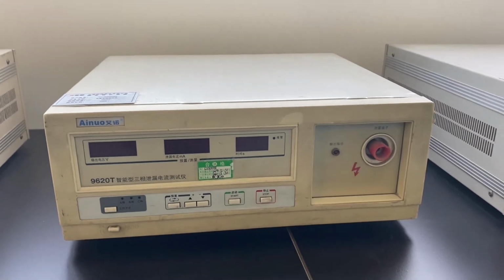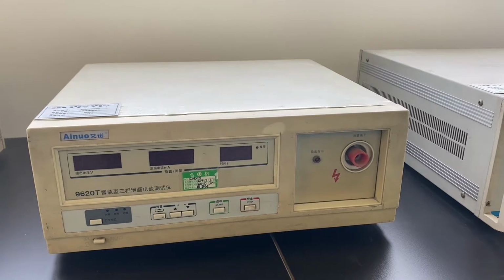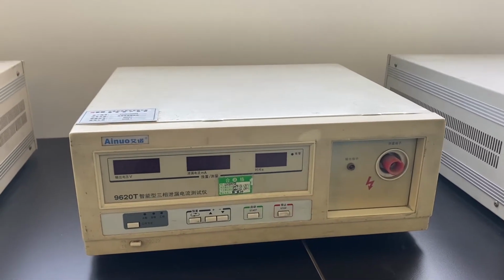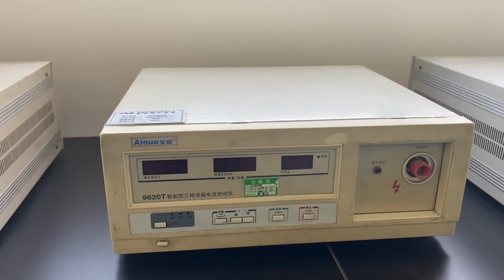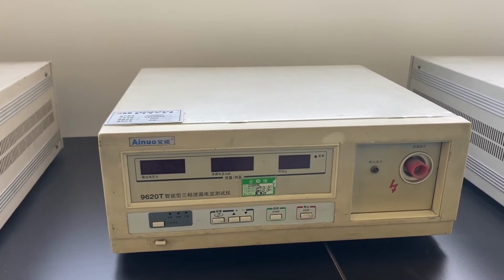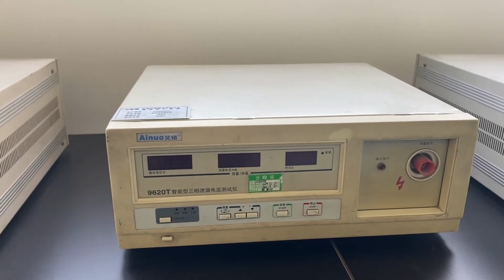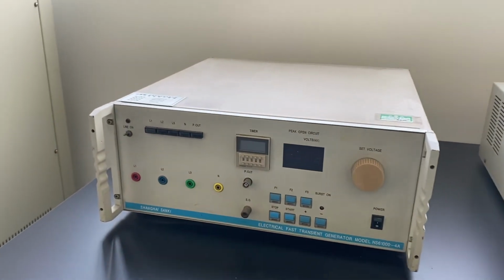This is for the voltage dip test. This device generates a voltage signal of 1% to 100% that simulates an instant increase or decrease, which is loaded into the device circuit to test whether the electronic system is reset or shut down when the voltage is instantaneously unstable.